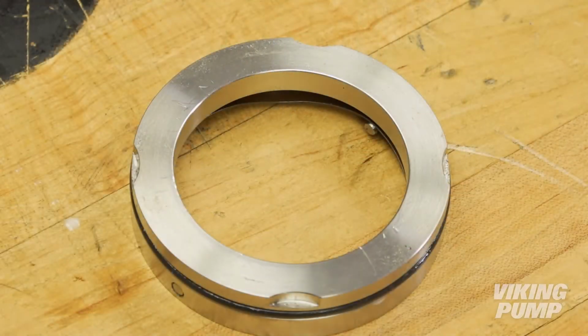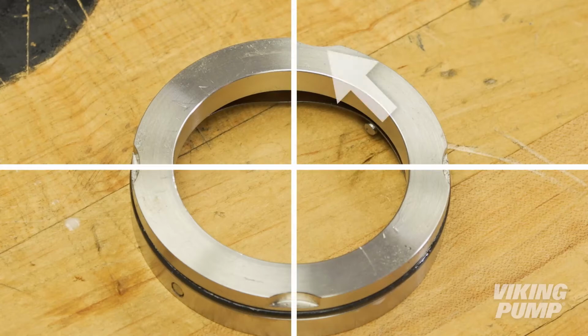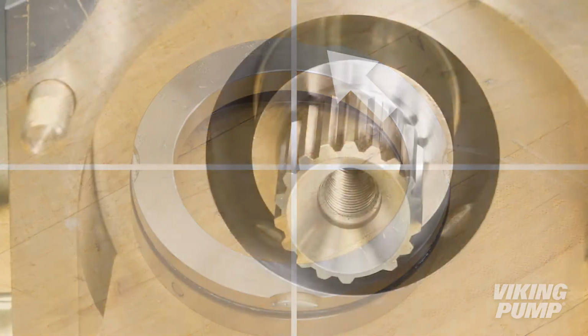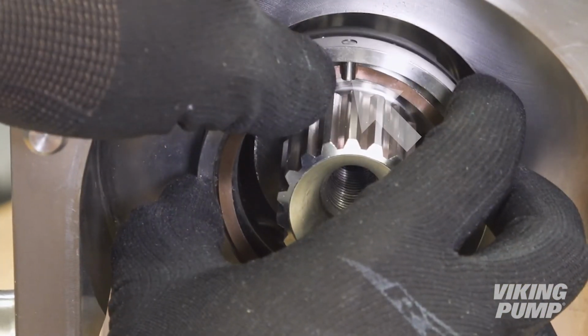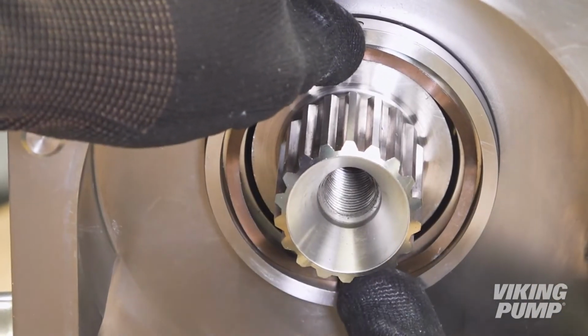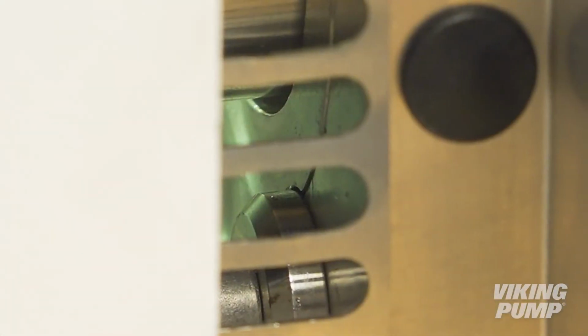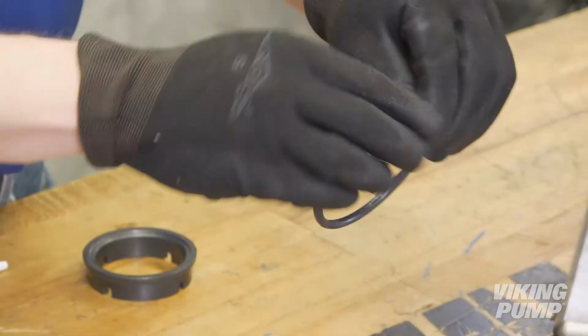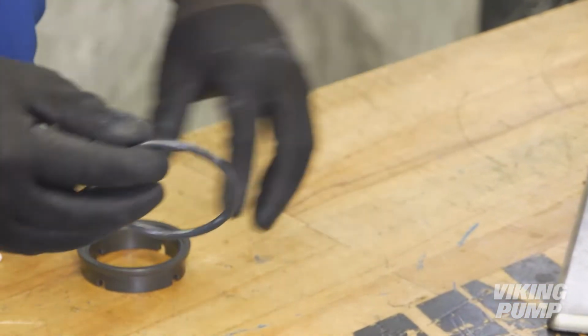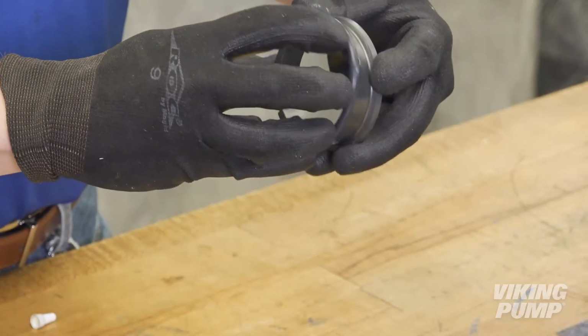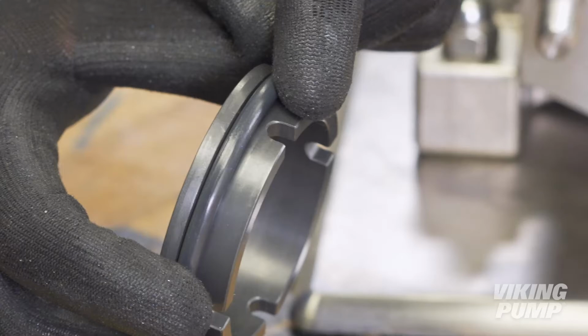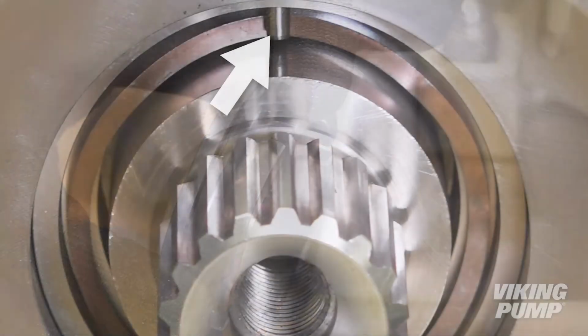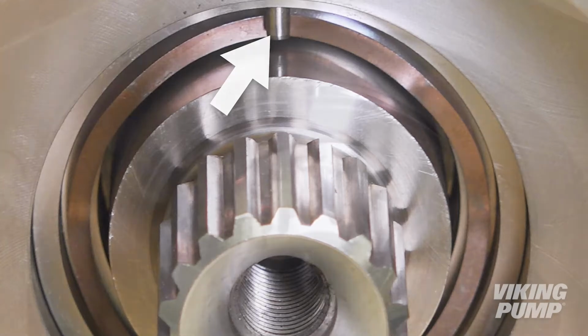To identify the offset cutout, lay the seal holder face down. For this holder, it is located here. When inserting the seal housing, orient the pins vertically at the 12 o'clock and 6 o'clock positions, with the offset cutout toward the middle of the rotor case. Press in and adjust as necessary until the seal housing is flat at the bottom of the bore and fully engaged with the seal washers. Lubricate and install the seal face O-ring. Press each static seal face into the seal housing, making sure to align the slots in the seal face with the anti-rotation pins in the seal housing.